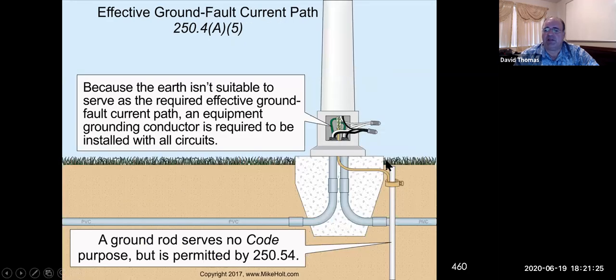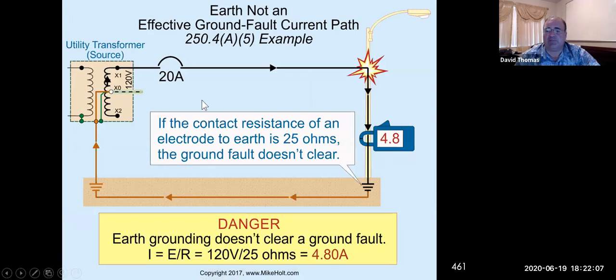Okay, and the purpose of the ground rod is if the lightning were to hit the pole, that the lightning would actually be diverted to earth through this pole and not into the electrical system through the equipment ground. That's the whole main purpose of doing it this way. If you've done metal fences before, they also do that for large metal fences that go around permanent ones. A lot of facilities like high security areas will do metal fencing. You have to run those ground rods also. So for lightning purposes, you ground it and have a place for it to travel down to earth instead of down the fence and possibly hurt somebody.